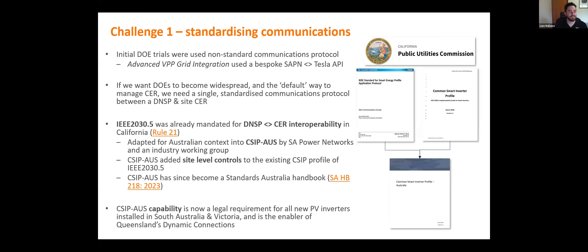Challenge one was standardizing communications protocols. Our first DOE trial with Tesla used a bespoke SAPN-to-Tesla API that wasn't suitable for use anywhere else. We wanted this to become statewide or national, so we needed a single standardized way to communicate between a DNSP and all devices at a home. We scanned globally and the leader in this space was the IEEE 2030.5 standard, already mandated for interoperability between a network and site in California under Rule 21 — a huge player in the energy space often setting international precedents.